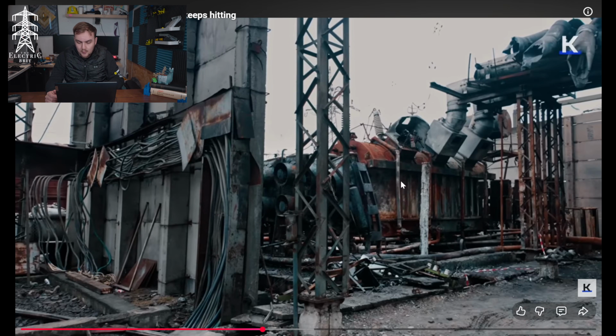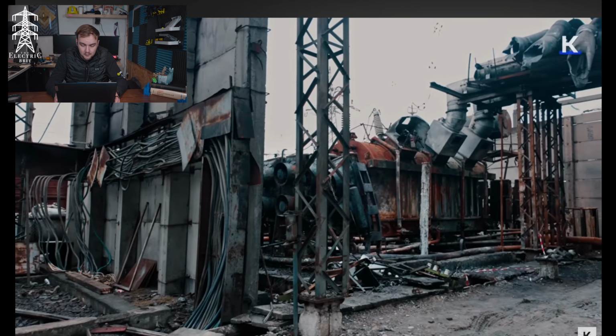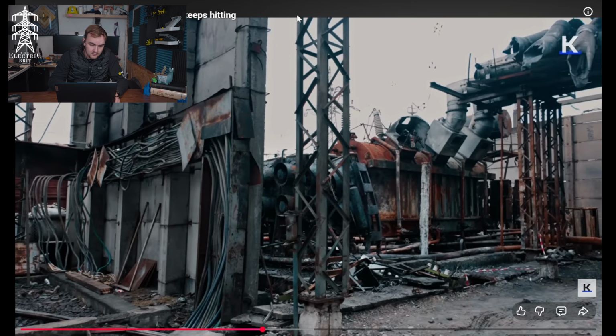These transformers are filled with oil, and it's nearly always flammable oil, so when that goes up it causes a lot of mess as well. These blast walls are one of the passive protections you can put in place to protect other assets adjacent on the other side of the wall from damage if that one transformer fails.